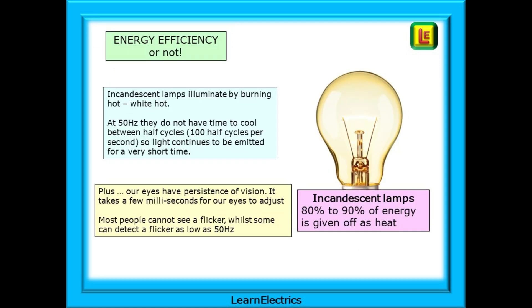Before we move on to LED lamps, let's take a look at incandescent lamps, which are not energy efficient. Incandescent lamps illuminate by burning hot — white hot. At 50 Hz, they do not have time to cool between half cycles, which is 100 half cycles per second. So light continues to be emitted for a very short time after the power is removed, and then the next half cycle arrives. Plus, our eyes have persistence of vision — it takes a few milliseconds for our eyes to adjust to any changes in light, and so most people cannot see a flicker. But there are some people who can detect a flicker as low as 50 Hz. And the big drawback with incandescent lamps: 80% to 90% of the energy used is given off as heat.